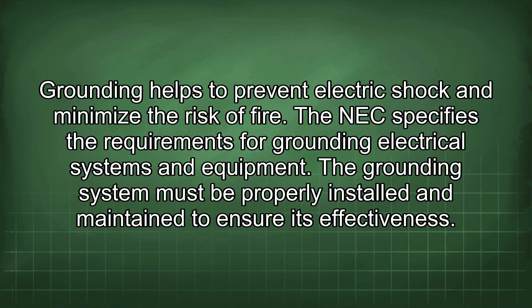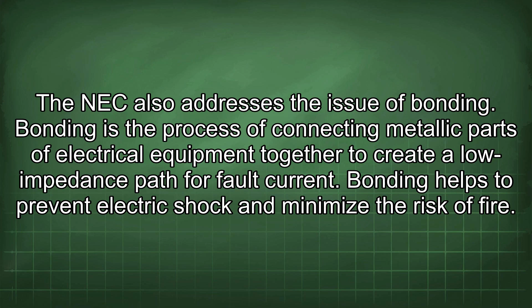The NEC also addresses the issue of bonding. Bonding is the process of connecting metallic parts of electrical equipment together to create a low impedance path for fault current. Bonding helps to prevent electric shock and minimize the risk of fire. The bonding system must be properly installed and maintained to ensure its effectiveness.